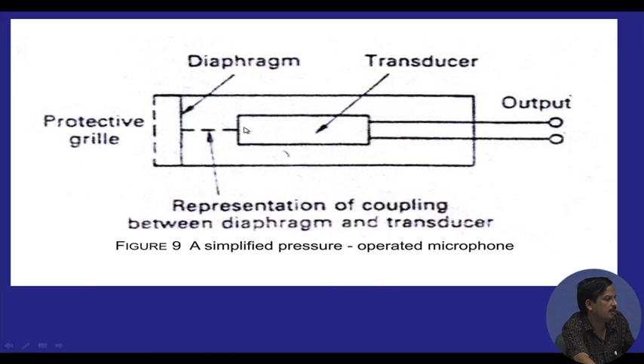when the wavelength is comparable to or less than the diameter, sound incident at 90 degrees may show phase cancellation, and differences may be introduced at high frequency for sound arriving at 180 degrees. If the sound arrives at 180 degree phase shift, there may be cancellation of the sound. If it is the same phase, it will be amplified, added up as an arithmetic sum. If it is opposite phase, it will be destructive. To avoid that, we make a small aperture here, with a small passage for the air pressure, so that the 180 degree sound also comes in here.